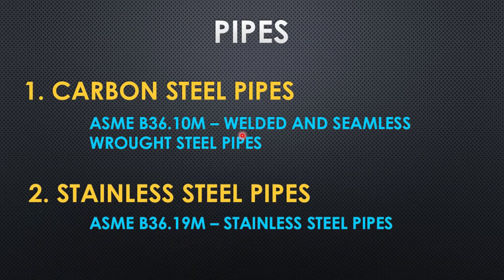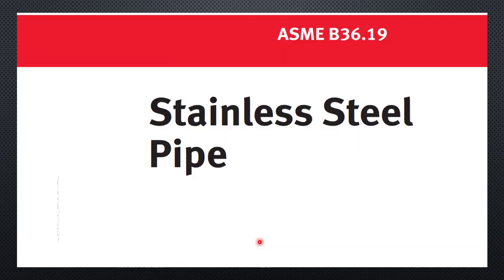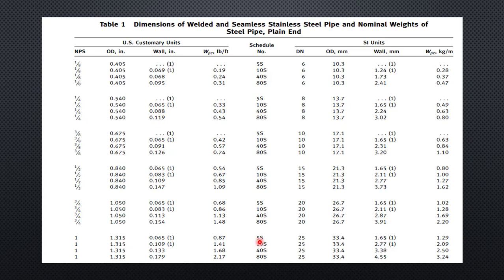Now let's go to stainless steel pipes. Stainless steel pipe dimensional details you will get from ASME B36.19M, which covers stainless steel pipes — this is how the cover page looks. Similar to carbon steel, you will get all these details from Table 1 of this standard: the pipe size, OD, wall thickness, and weight. Like the carbon steel standard, it is also available in both imperial and metric units.